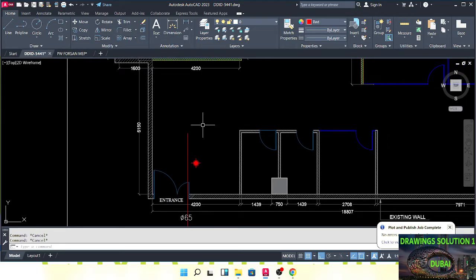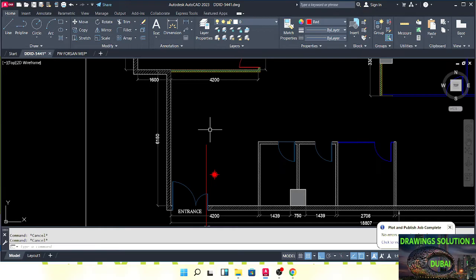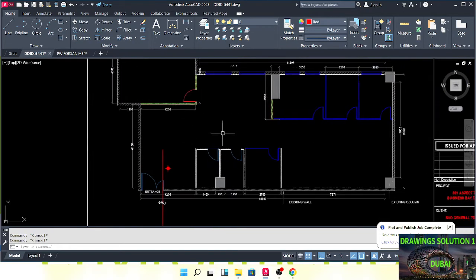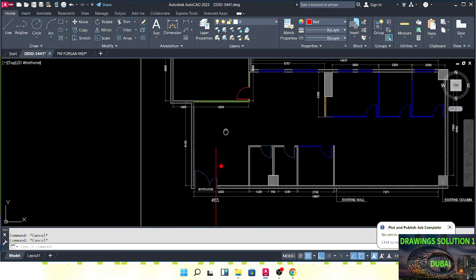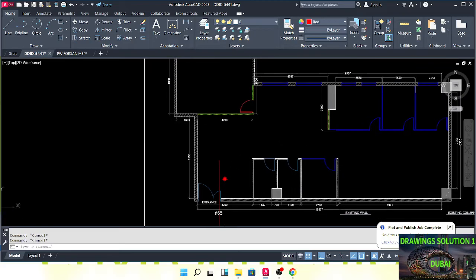Pendant sprinklers we normally install in the ceiling or in the open ceiling. We need upright sprinklers if the distance from the ceiling to the slab is more than 1.5 meters. For this office we don't have that much distance from ceiling to slab, so we only use pendant sprinklers here.